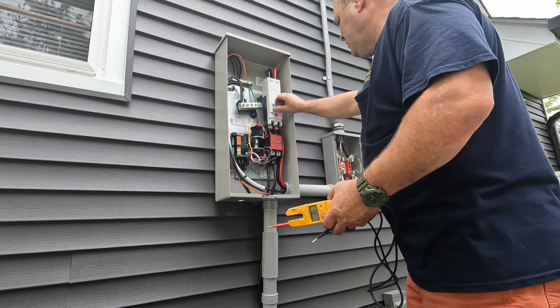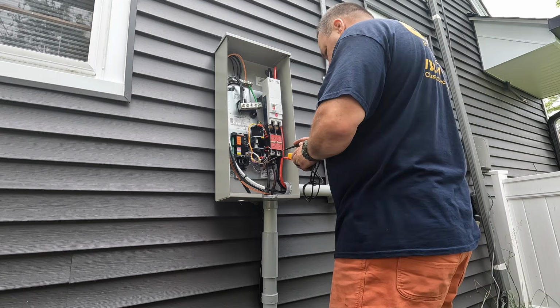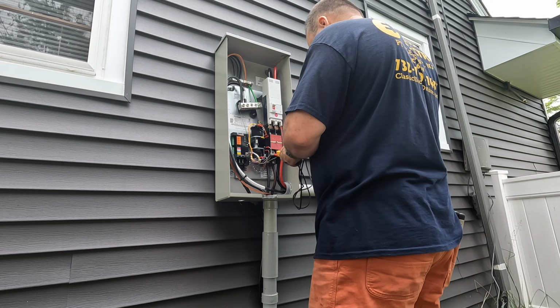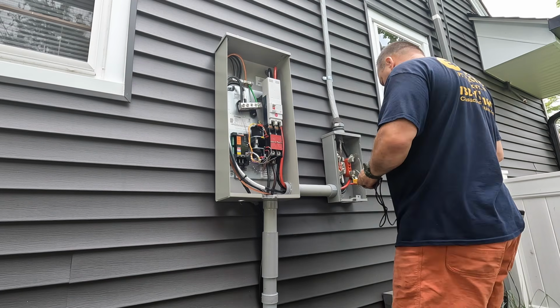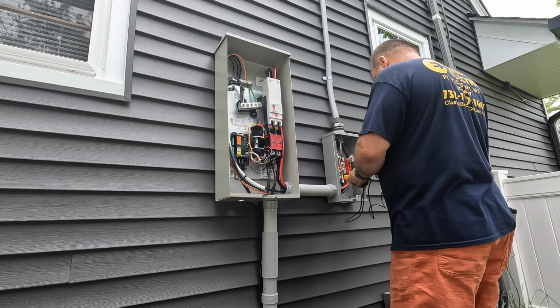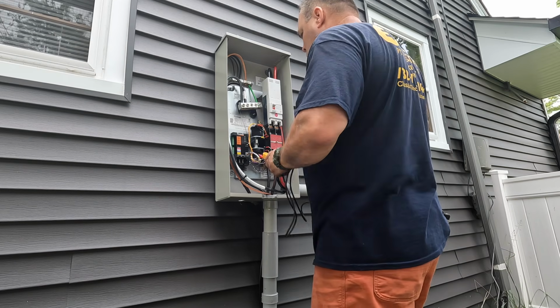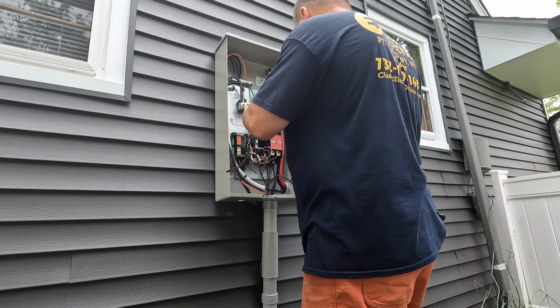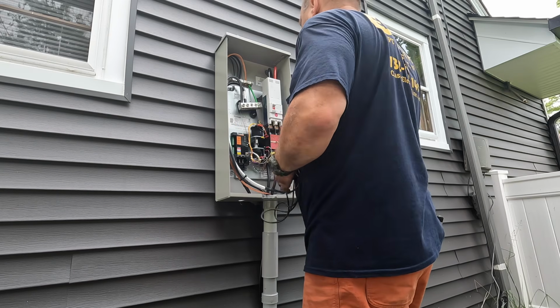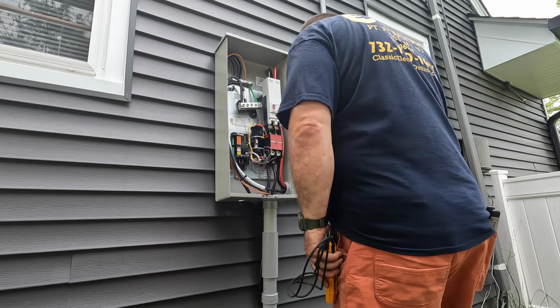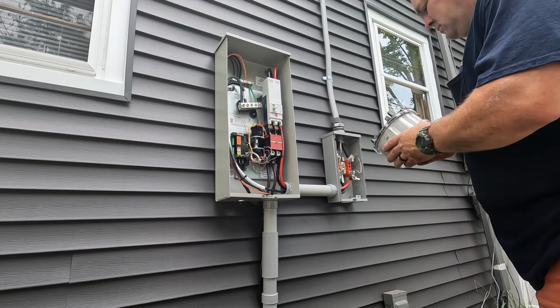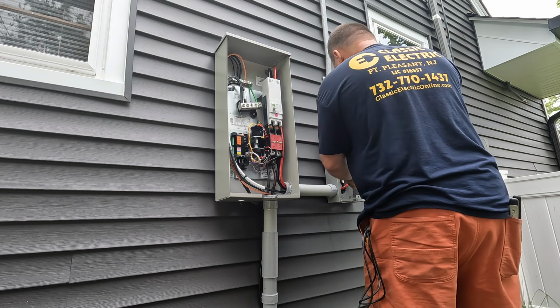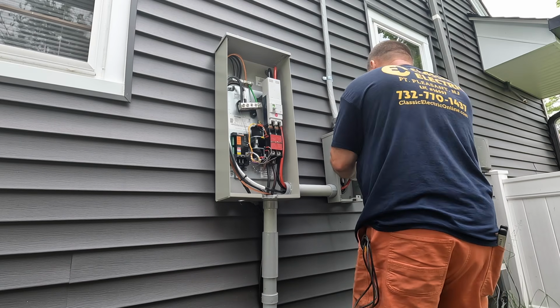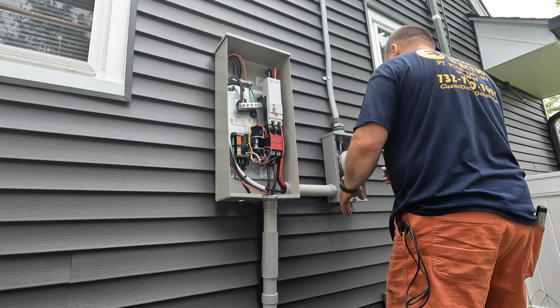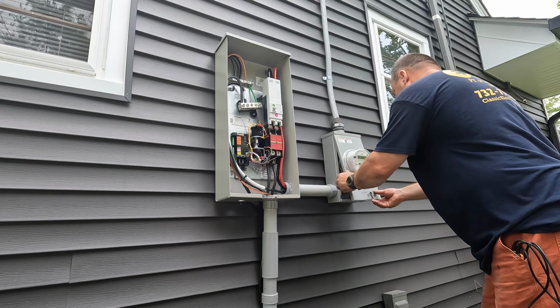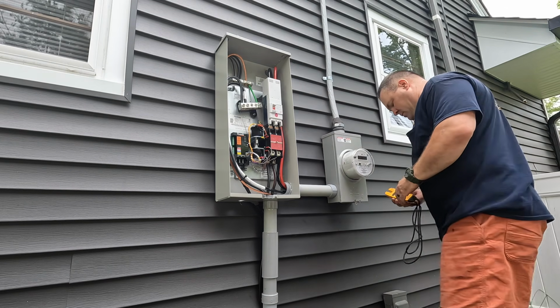Of course, once my final connections are made, before I energize the electrical work here, I'm just going to check for any short circuits, any continuity that shouldn't be there, before I go ahead and put the meter in. And yes, I do understand the danger in putting a live meter with live conductors. This is why I'm checking it before I put the meter in. Once I put the meter in, then the load side of the meter lugs are live, and so is the incoming line side to our automatic transfer switch. And then once I energize the transfer switch, there should be power downstairs at our panel. We'll go downstairs, we'll turn on all of the circuit breakers, and that'll be the end of the job.